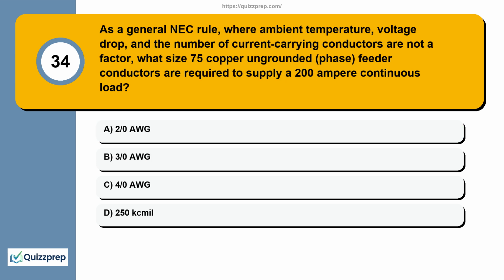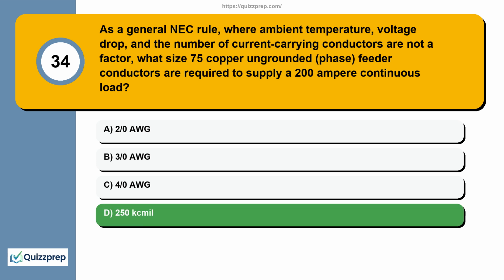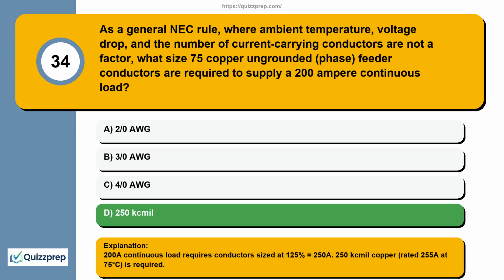Question 34. As a general NEC rule, where ambient temperature, voltage drop, and the number of current carrying conductors are not a factor, what size 75 degree copper ungrounded (phase) feeder conductors are required to supply a 200 ampere continuous load? 2/0 AWG, 3/0 AWG, 4/0 AWG, 250 kcmil. A 200 A continuous load requires conductors sized at 125%, which equals 250 A. 250 kcmil copper, rated 255 A at 75 degrees Celsius, is required.